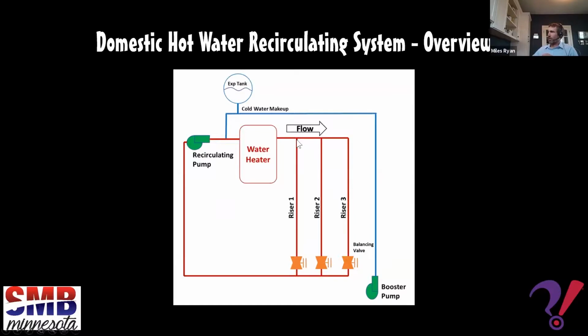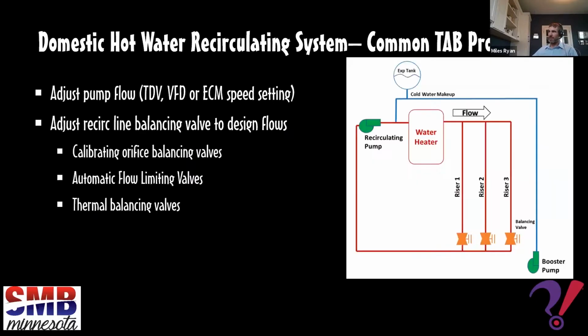Now, riser 1 is kind of the path of least resistance. So more flow is going to go through the path of least resistance unless you put balancing valves on each of these paths of flow to make sure that they all get their fair share of flow and all of the different fixtures throughout the facility are having hot water available on demand in a reasonable time frame. I'm going to turn over to Rebecca to talk about some of the issues we see with domestic hot water recirculating systems. Oh, actually, I jumped the gun. Let me turn over to Mark to talk about the TAB procedures that would be associated with that.